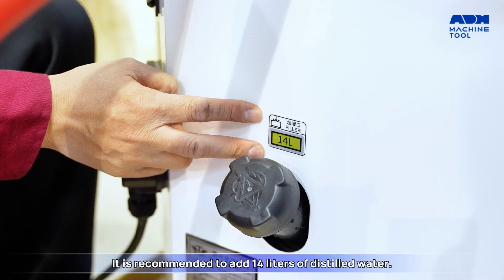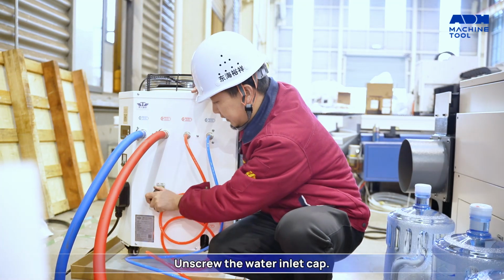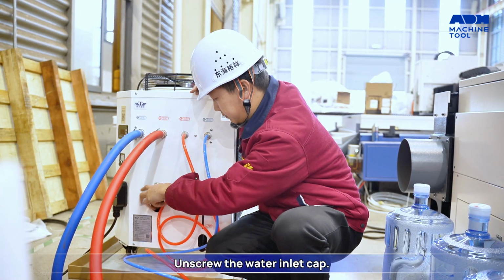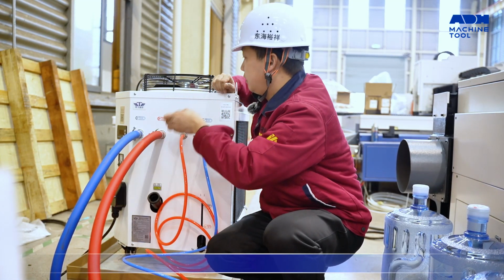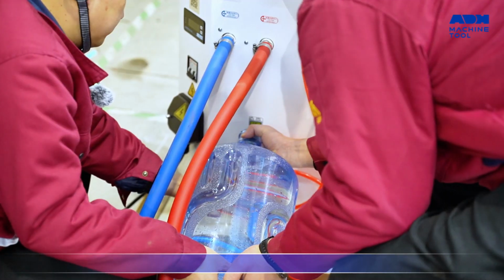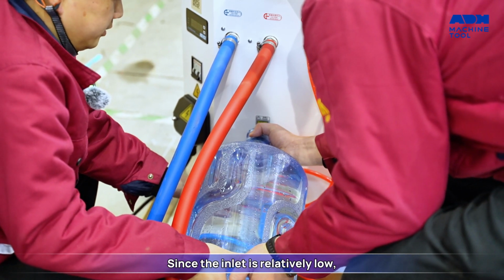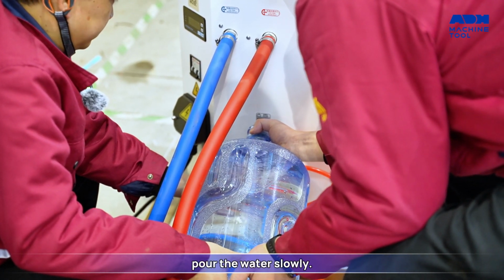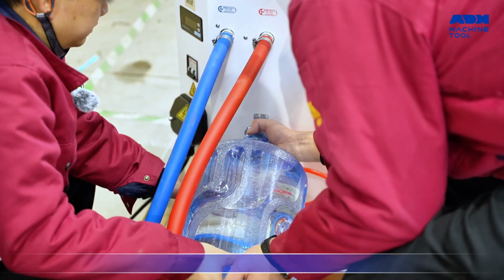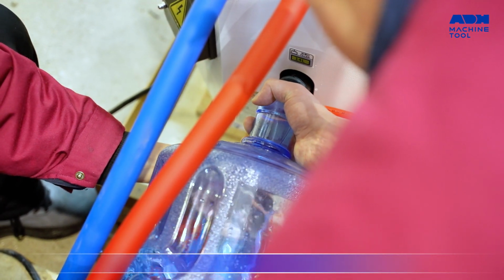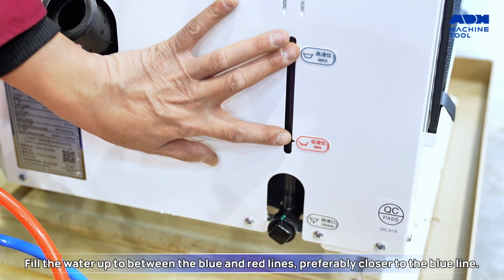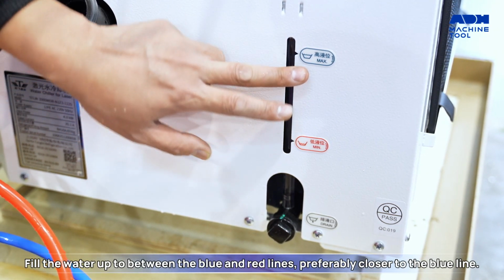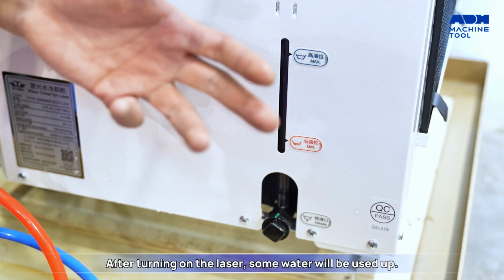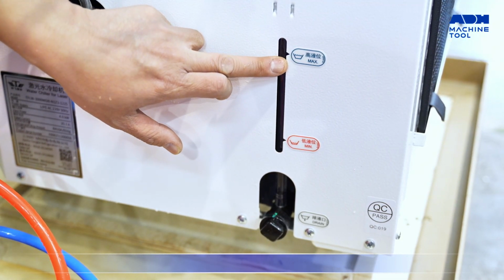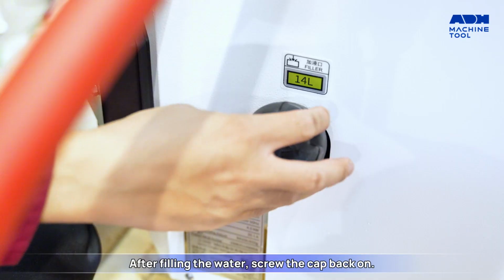It is recommended to add 14 liters of distilled water. Unscrew the water inlet cap. Since the inlet is relatively low, pour the water slowly. Fill the water up to between the blue and red lines, preferably closer to the blue line. After turning on the laser, some water will be used up. After filling the water, screw the cap back on.